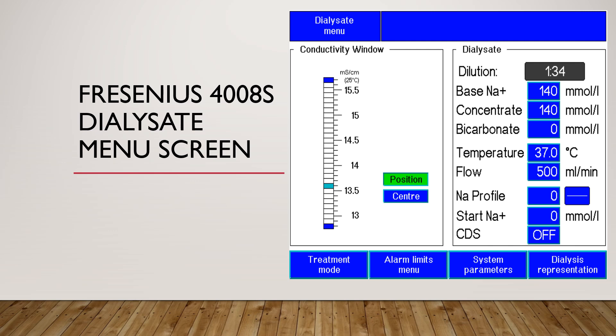For example, your A-part solution usually contains 103 millimole per liter sodium, and the bicarbonate or B-part contains 35 millimole per liter sodium. In this scenario, your base sodium will be 103 plus 35, which equals 138 millimole per liter.